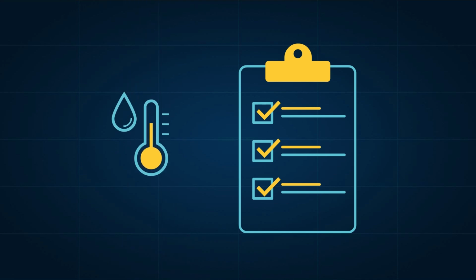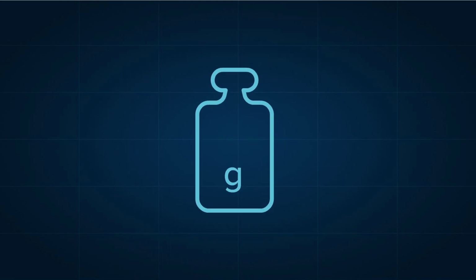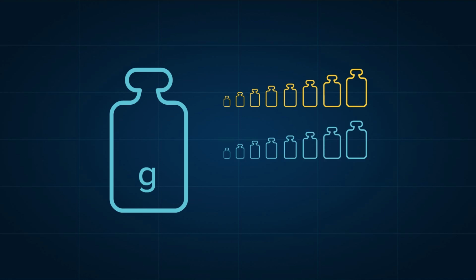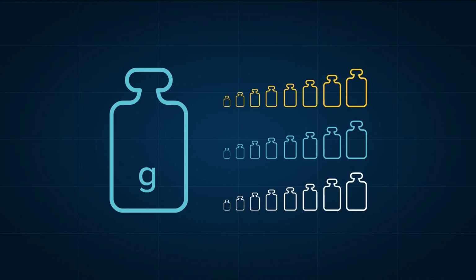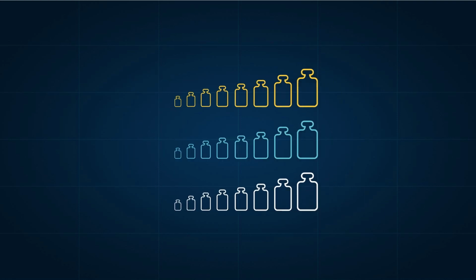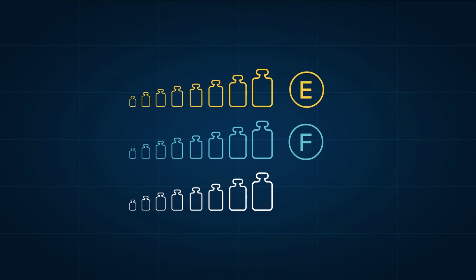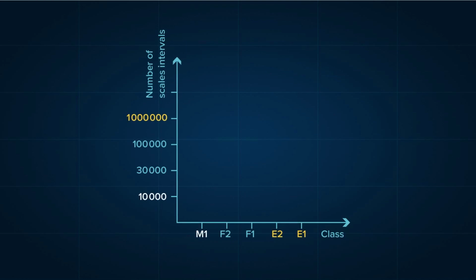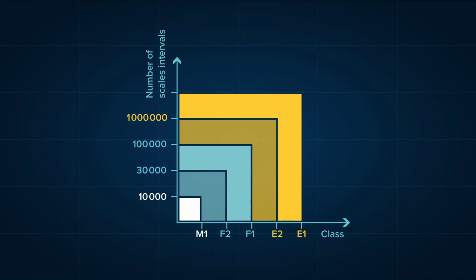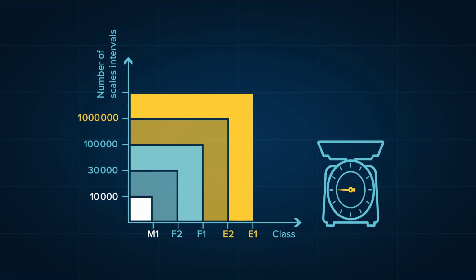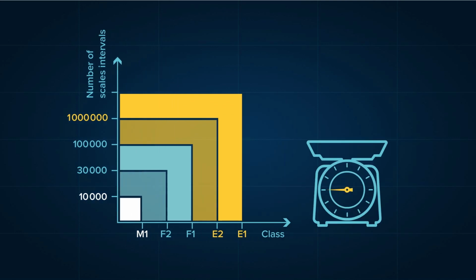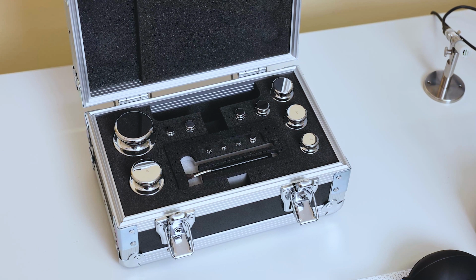For the mass standards, there are several classes defined by the international recommendation OIML R111-1. They are divided into three categories: the classes E, F and M. Weights of Class E have the best accuracy. In order to be able to calibrate a scale, the operator must have mass standards, with a class adapted to the specifications of the scale. Indeed, a scale with a resolution to the nearest milligram will have to be calibrated with Class E or F weights, depending on its maximum capacity.